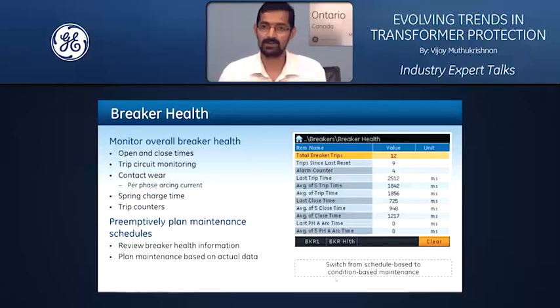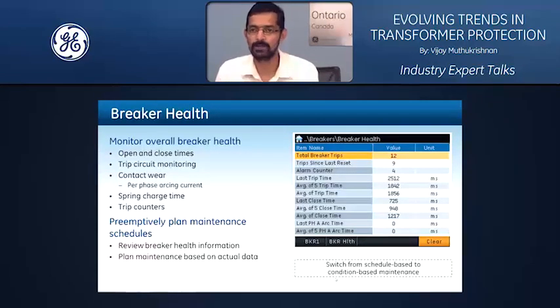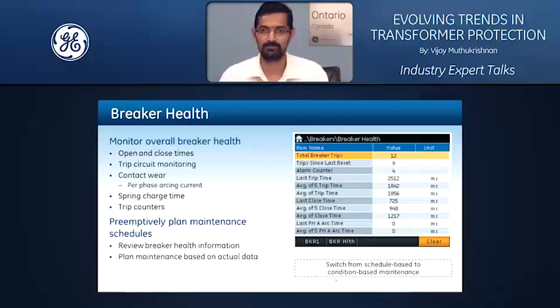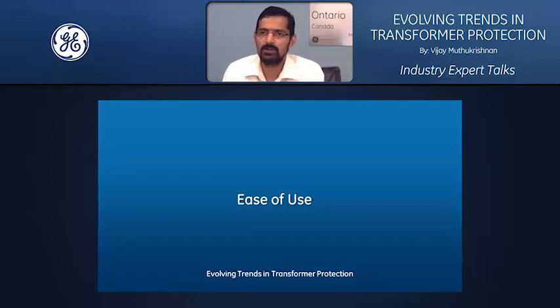The idea behind this set of breaker health monitoring functionality is that, by looking at this data effectively over a period of time, you can shift from schedule-based maintenance to condition-based maintenance. That's the idea behind giving you breaker monitoring functionalities, breaker health report type of features, as part of 8 series functionality. Now, this concludes what we can do in the 845 relay on monitoring and diagnostic features. Moving on, we talked about the reliability of protection. We talked about comprehensive coverage for applications. We talked about interoperability, security, and monitoring and diagnostics.